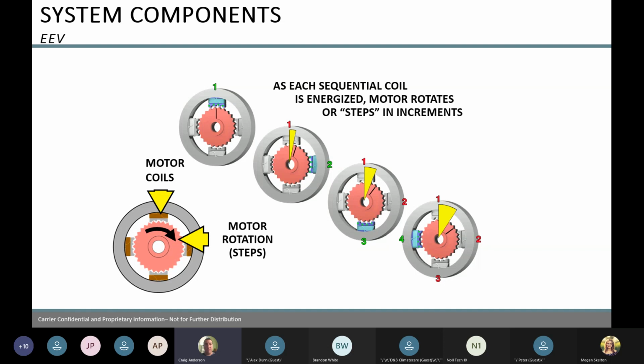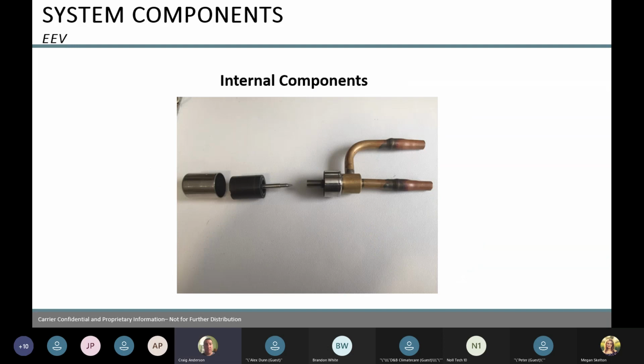So we need to be mindful that these sensors are in the proper location. They're not hanging off the pipe. They need to be in the proper place for everything to operate. Internal components: this is all it looks like inside if you opened up an EE valve. I've been told by the tech department at ICP that EE valves very rarely fail. From what I'm told, they've seen maybe two fail within a year.